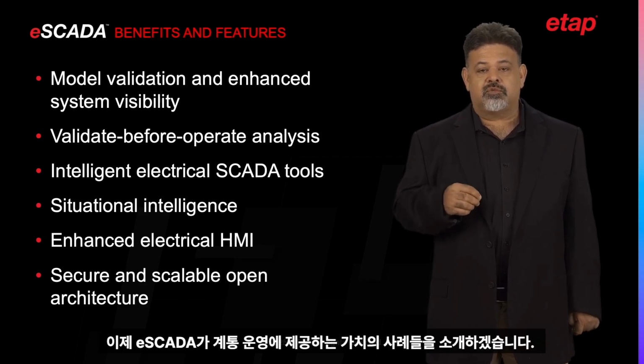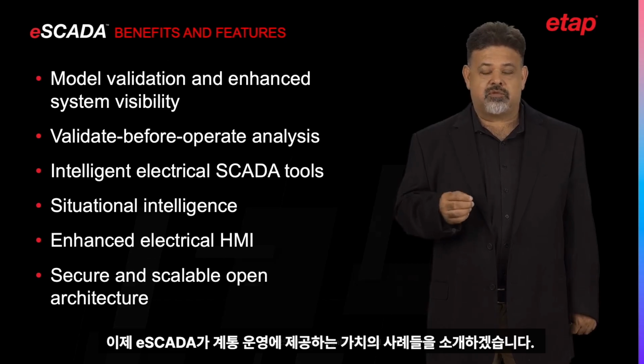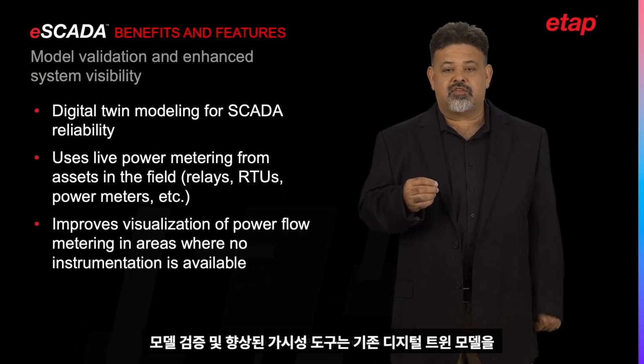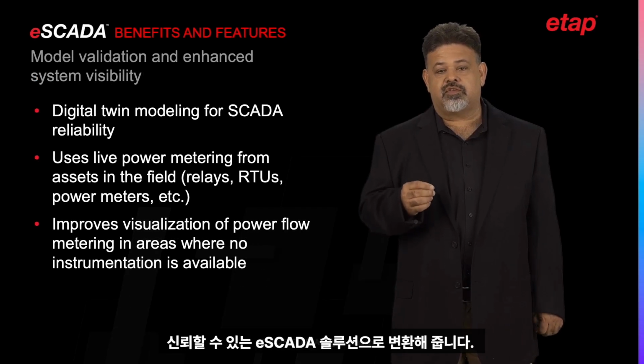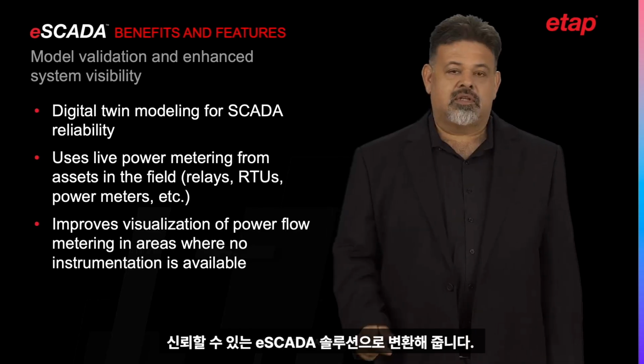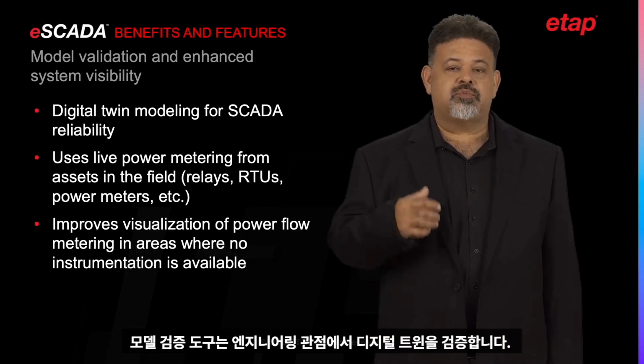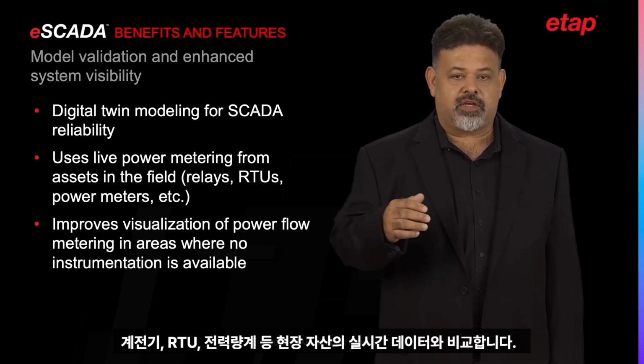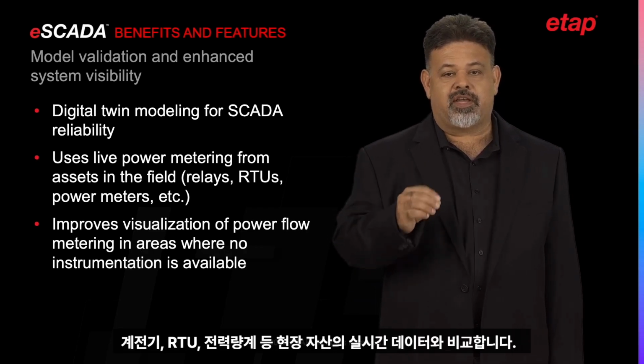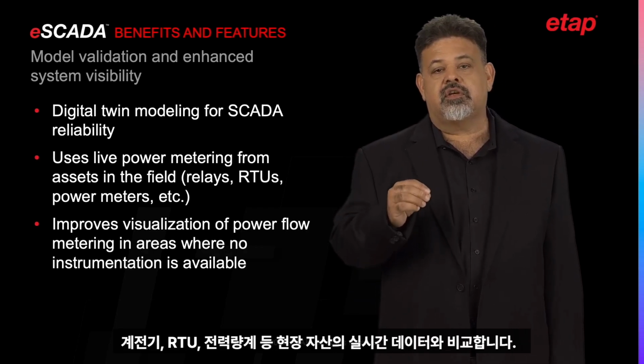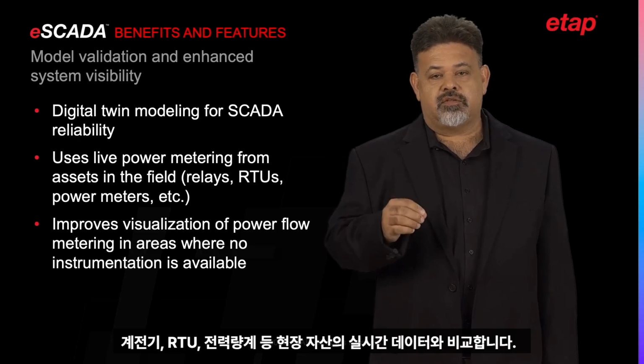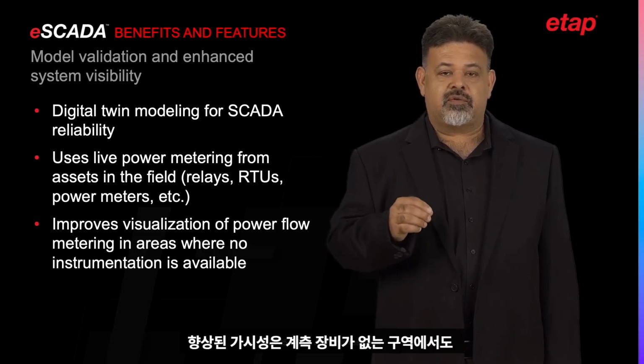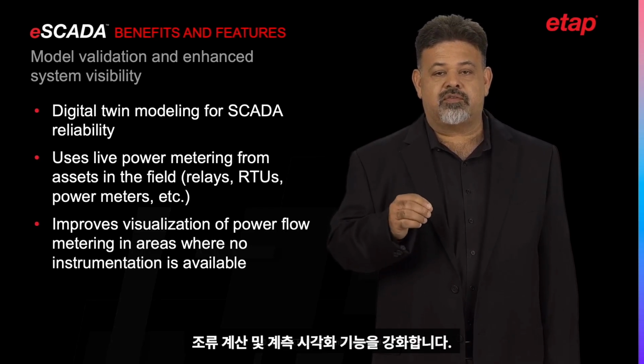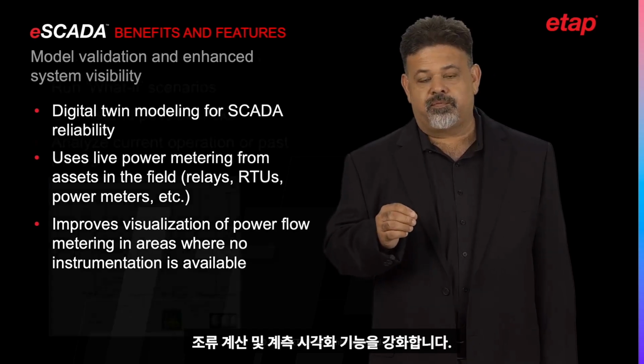Now I will introduce some of the examples of the value that ETAP eSCADA brings to electrical systems operation. Model validation and enhanced system visibility tools transform your existing digital twin model into a reliable eSCADA solution. The model validation tool uses an engineering perspective to validate the digital twin against live power and metering from assets in the field such as relays, RTUs, power meters. The enhanced visibility increases the visualization of the power flow metering in areas where there is no instrumentation available.